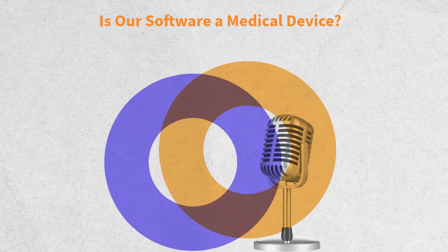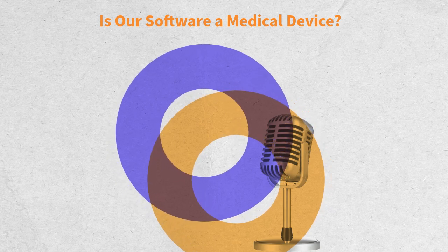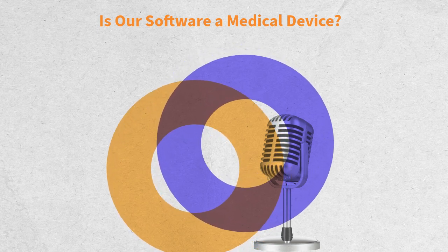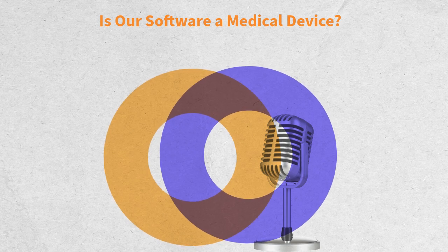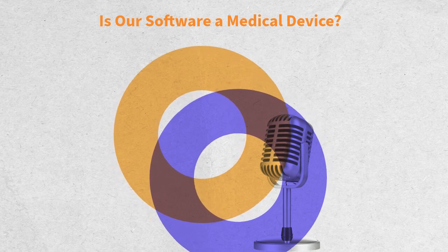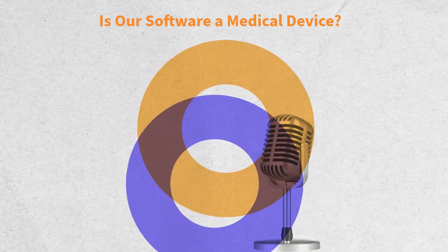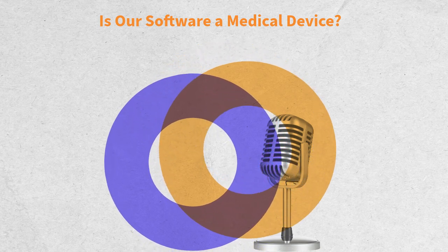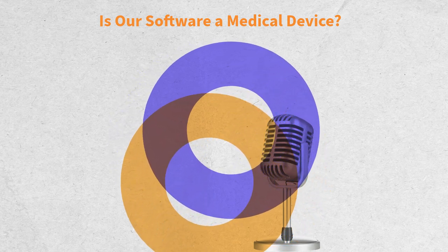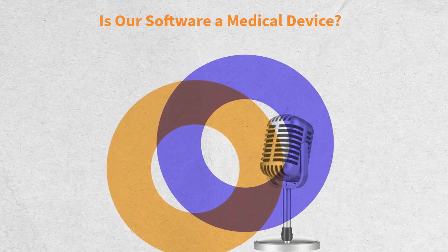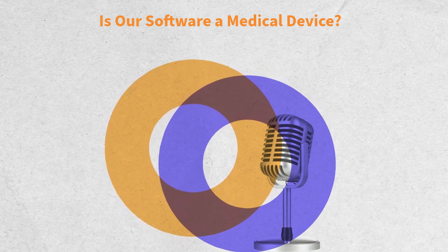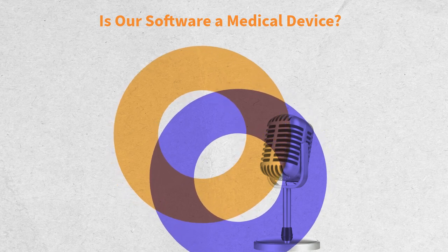What are the documental obligations for MD software? An MD software requires a set of mandatory documents with different level of details based on the risk class. The main includes technical dossier, the core of conformity, where you describe the architecture, scope, requirements, tests, and the whole technical and clinical validation, risk analysis, risk management, according to ISO 14971, to map risks, severity, probabilities, and define mitigation measures.